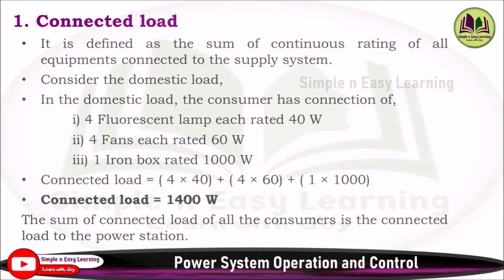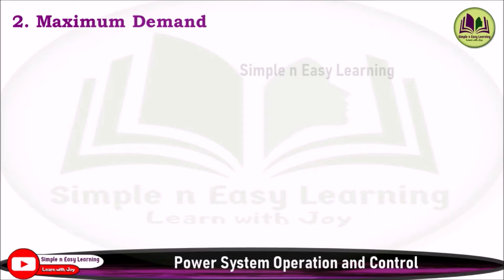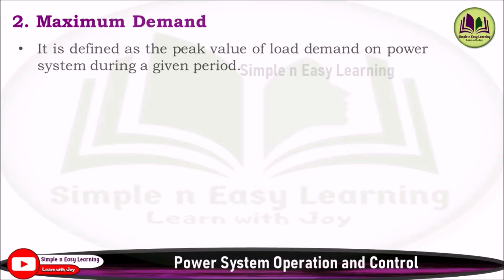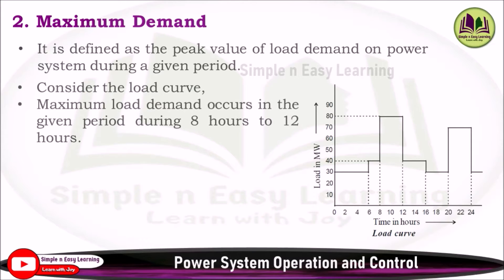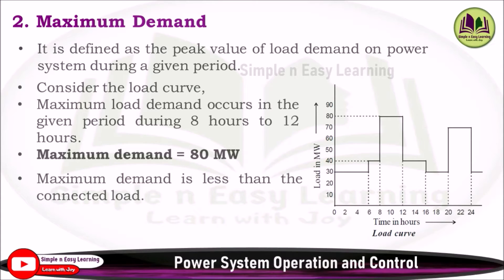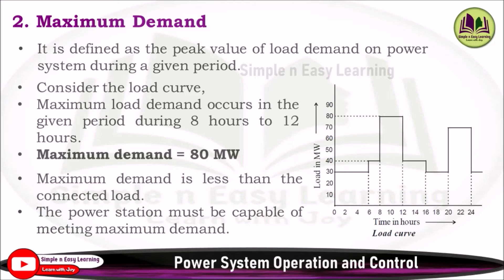The sum of connected loads of all consumers is the connected load to the power station. Second: maximum demand. It is defined as the peak value of load demand on the power system during a given period. For example, on a 24-hour load curve, if the peak occurs during 8 to 12 hours at 80 megawatt, that is the maximum demand. Maximum demand is less than connected load, and the power station must be capable of meeting it.